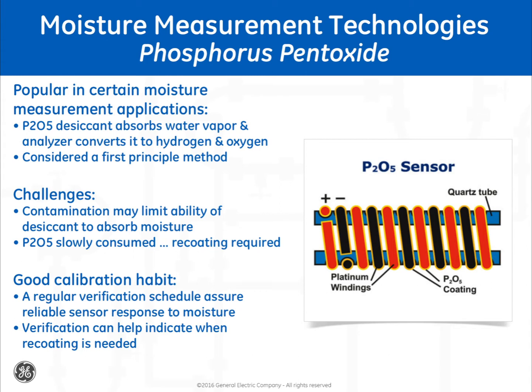Phosphorus pentoxide moisture analyzers are popular in certain moisture measurement applications. The theory is that the P2O5 desiccant absorbs the water vapor, and the analyzer converts this to hydrogen and oxygen. Anything that can change the ability of the P2O5 to absorb moisture will impact the accuracy of the measurement. Many consider this a first principle method. Thus, they state that the sensor requires no calibration. At least one manufacturer states that the P2O5 is slowly consumed, eventually rendering it unable to respond to moisture, and that the sensor needs to be recoated.